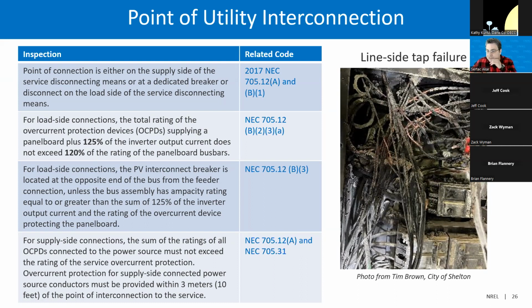So it is important to check these numbers. The labels can be used as reference, and an easy calculation can be done to see if this is within the limits of the overcurrent protection. Overcurrent protection for supply side connected power source conductors must be provided within 3 meters, or 10 feet, of the point of interconnection to the service. And here is an example of a line side tap failure that shows the significance of these inspections. If they are not properly inspected, this kind of result can happen, and this is a picture of a totally failed, burned line side tap.